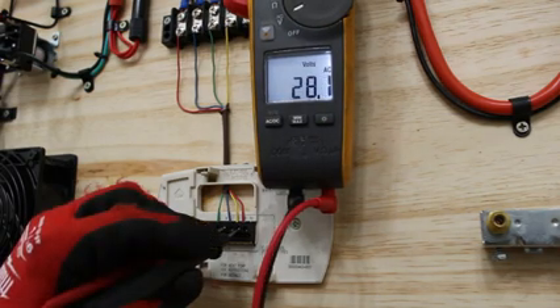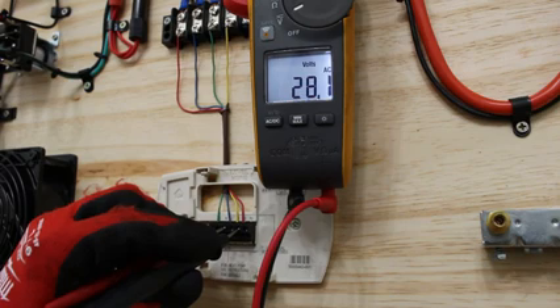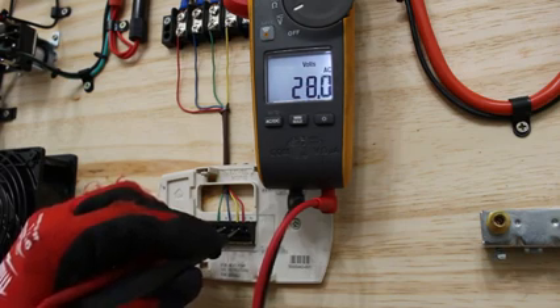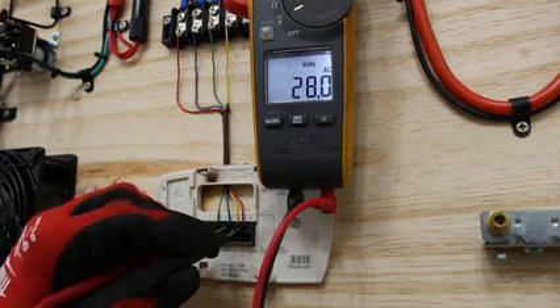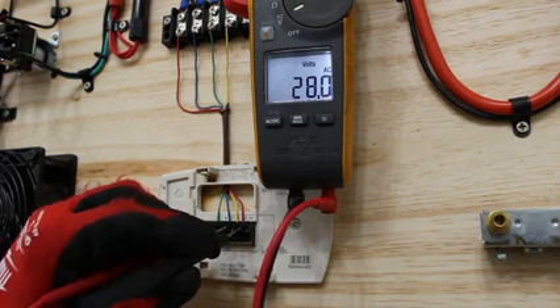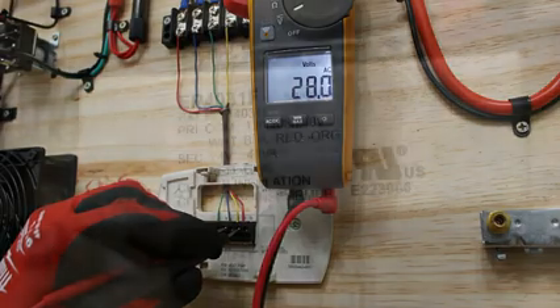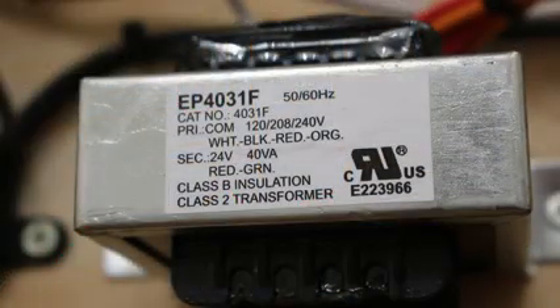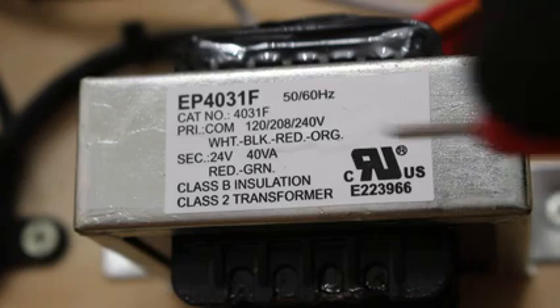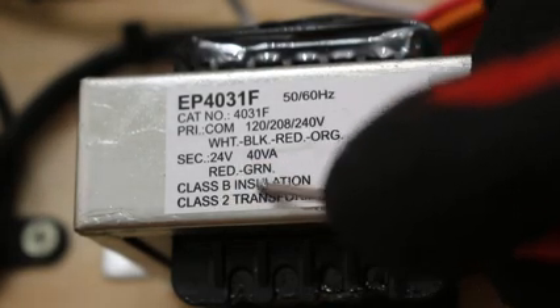If between R and C we didn't have 24 volts, now we have to further look into what's going on. Now we need to make sure, do we have voltage at our primary before we can actually say that this transformer is bad. No matter what kind of transformer you have, you're going to have two wires connected at your primary, and you're going to have two wires connected at your secondary. Your secondary, you don't really have an option. It's going to be your red and green, and this is always going to be your 24 volts.